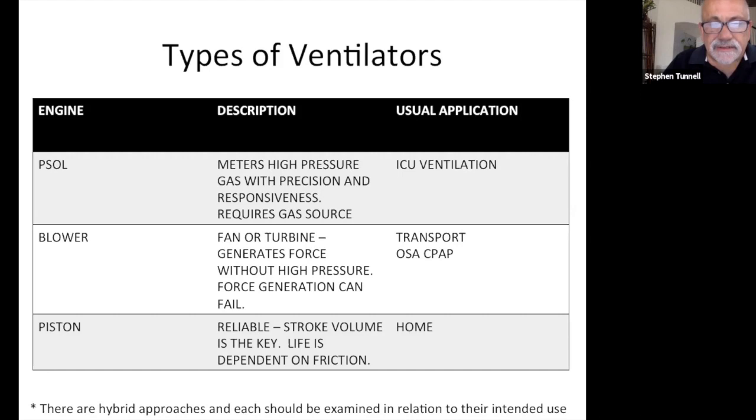Proportional solenoids are very fast in terms of responding to the patient, and they're very precise. They're considered the highest end of mechanical ventilation. They're considered the creme de la creme of mechanical ventilators, if such a thing can be.